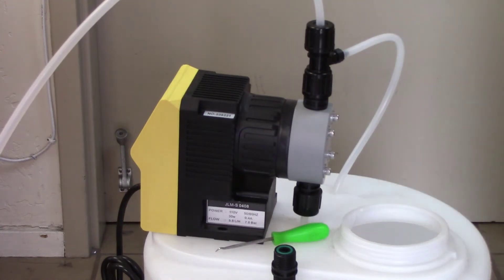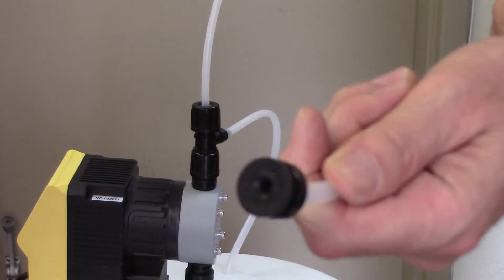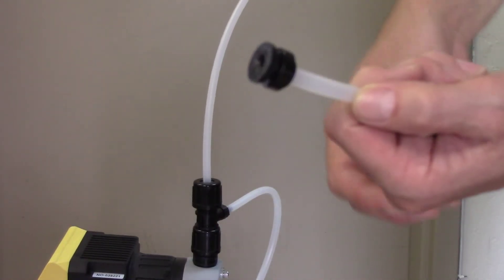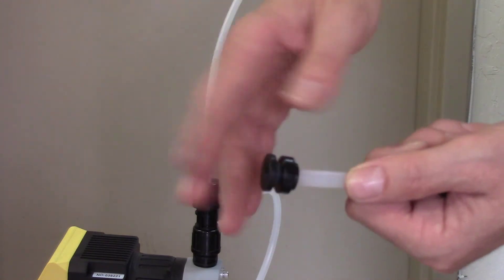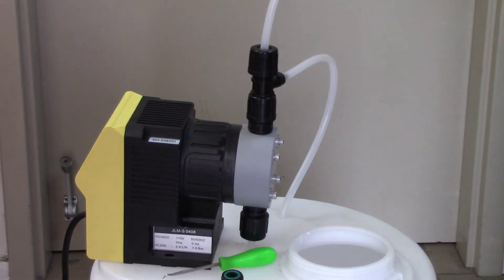Especially during the summer, everything starts heating up, so the tubing connections can be loosened where we have the cone and the collet attached to the tubing. If you see salting up around there, trim a quarter inch off the pipe nice and square like the other video shows you, and then redo your connection. A lot of times that's all it needs. Remember, if any of these connections stop being watertight, you're gonna have loss of prime issues. Part of the reason that you have loss of prime issues in the summertime is because water heats up and your fittings might move around.